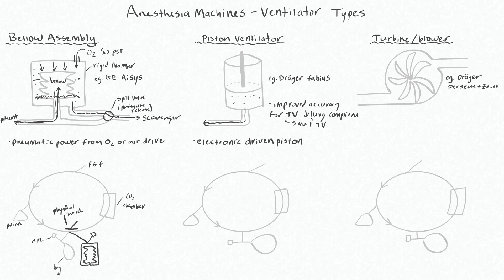One advantage of this is greatly improved accuracy for delivering tidal volumes, particularly when you have issues like decreased lung compliance or small tidal volumes like in the pediatric population — this would be very important. This is a fixed volume inside the cylinder, so you can imagine it will be more accurate in delivering a certain volume when it moves the piston up and down a certain amount.